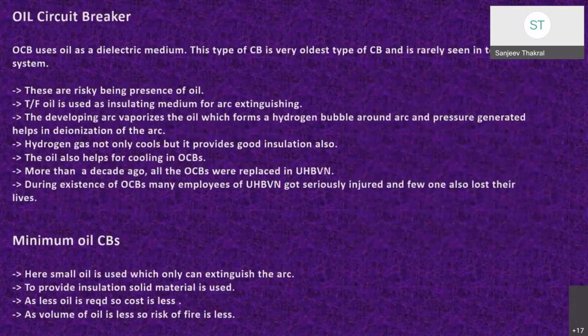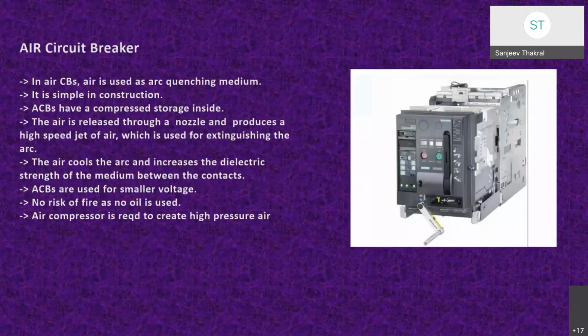Oil circuit breakers are of two types: bulk oil circuit breakers and minimum oil circuit breakers. In the minimum oil circuit breaker, a smaller amount of oil is used, so the volume is less, and so the risk of fire is less. Next is the air circuit breakers.